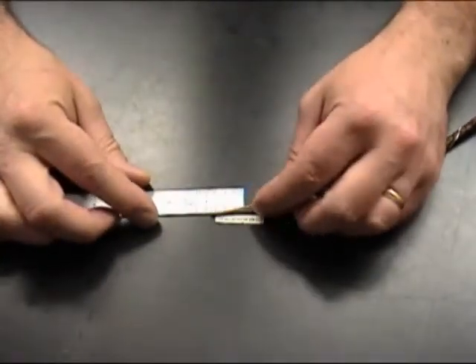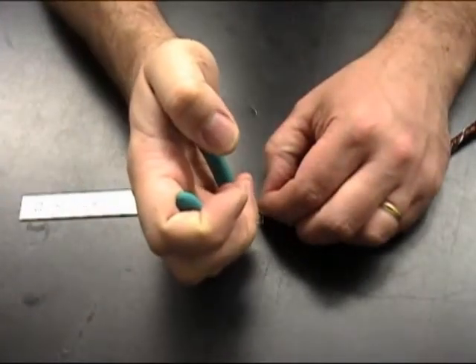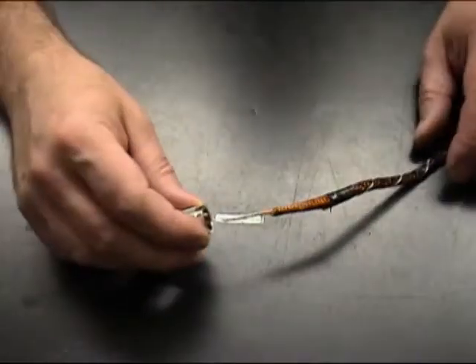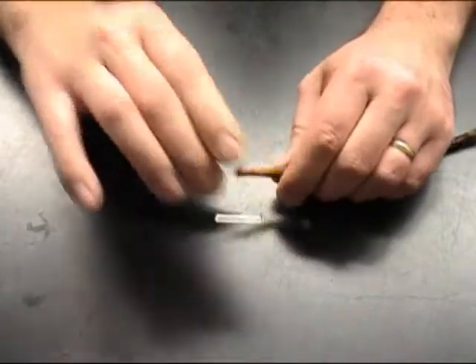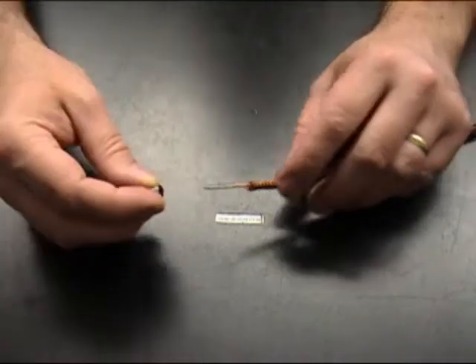Next we're going to remove about three quarters of an inch of the thin insulating material from the center conductor. Then we will slide on our coupling ring, making sure that we put the shoulder part of the coupling ring onto the cable first. Then we'll slide on our outer crimp ferrule or shield ferrule.